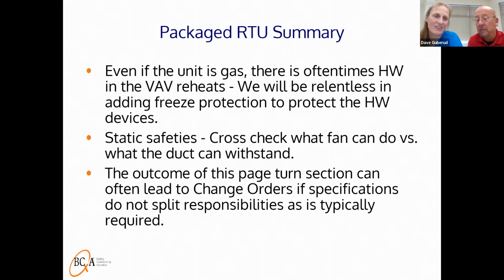Right, and I would also say on this, before you push the button, it's important to note we prefer hardwired freeze stats. We've had experiences where they argue to provide a software low limit, and on, of course, a nice design winter day, they lost communication and other things, and they ended up freezing a bunch of coils. If it was hardwired, that would have helped. It would have likely saved a bigger mess.